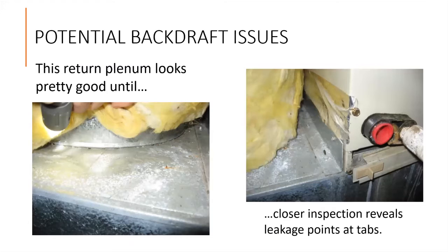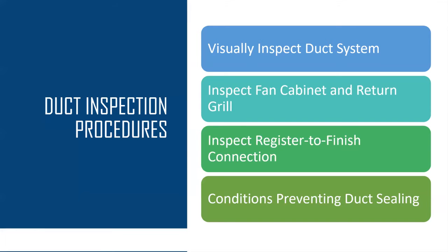Things that cause negative zone pressure and potential backdrafting issues include a return plenum that looks fine at first glance — but when you pull back the insulation, you can see leakage spots around the tabs of the start collar. Let these four key points guide your duct inspection procedures: visually inspecting the duct system thoroughly, inspecting around the fan cabinet and the return grill, inspecting where the register is and how it's finished with the finished surfaces, and making note of any conditions that might prevent duct sealing.